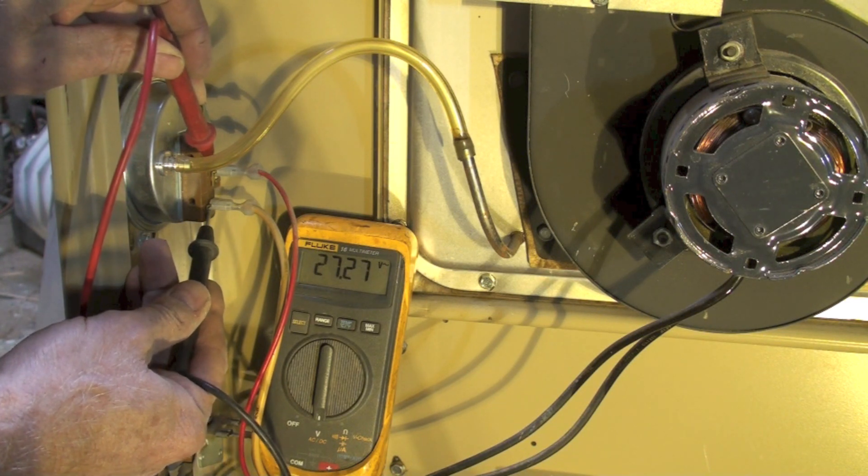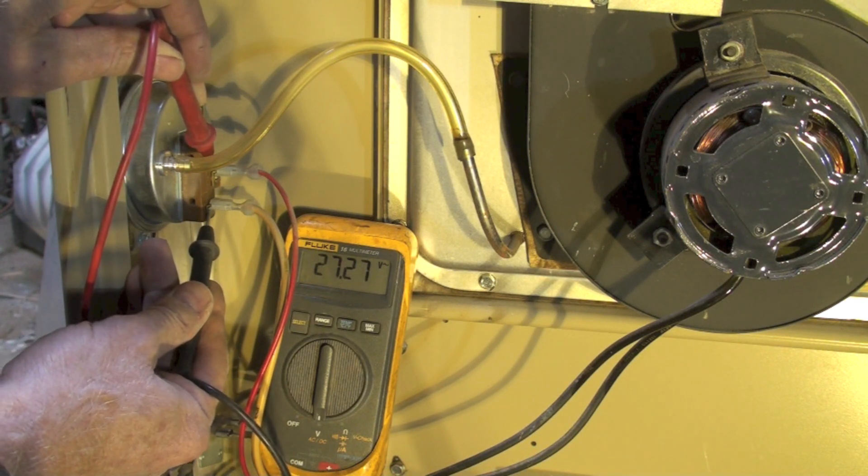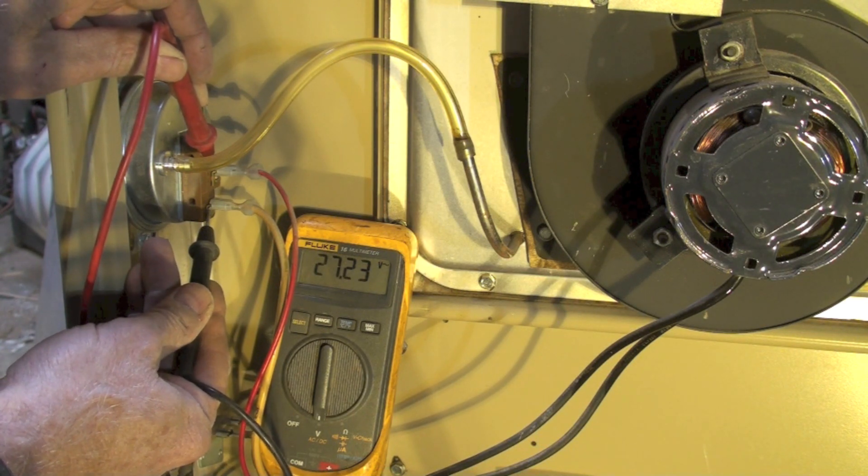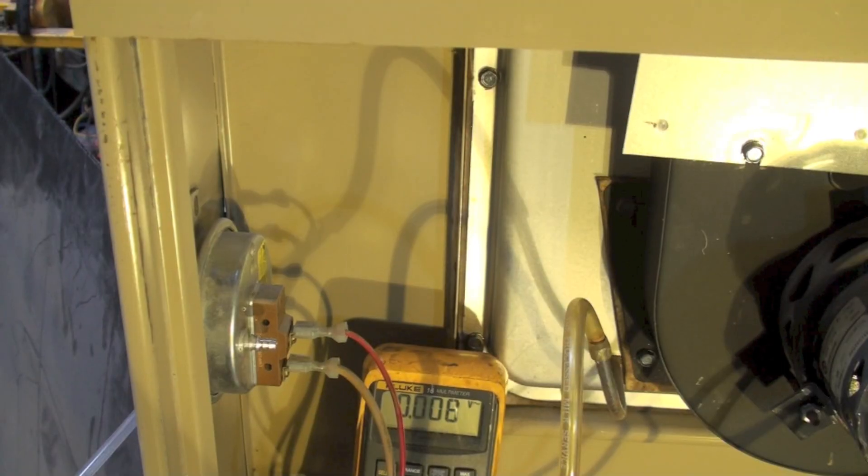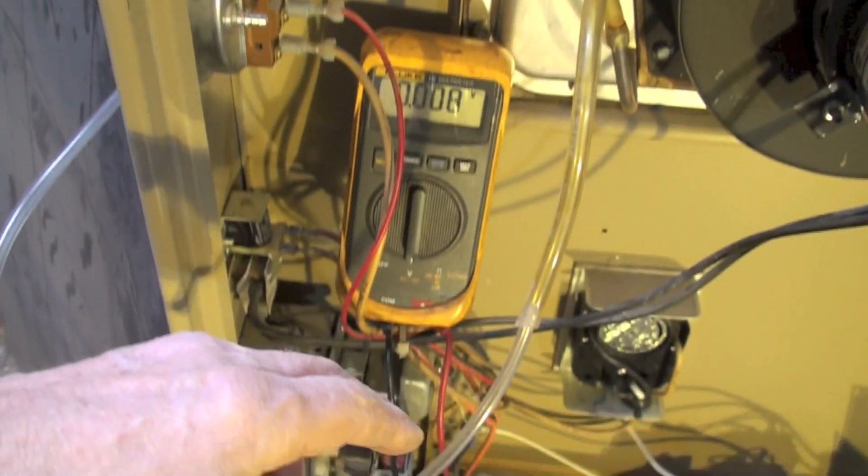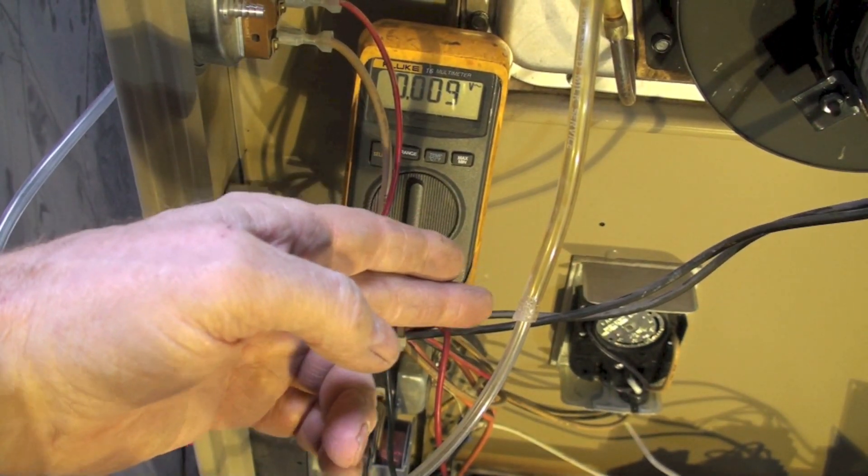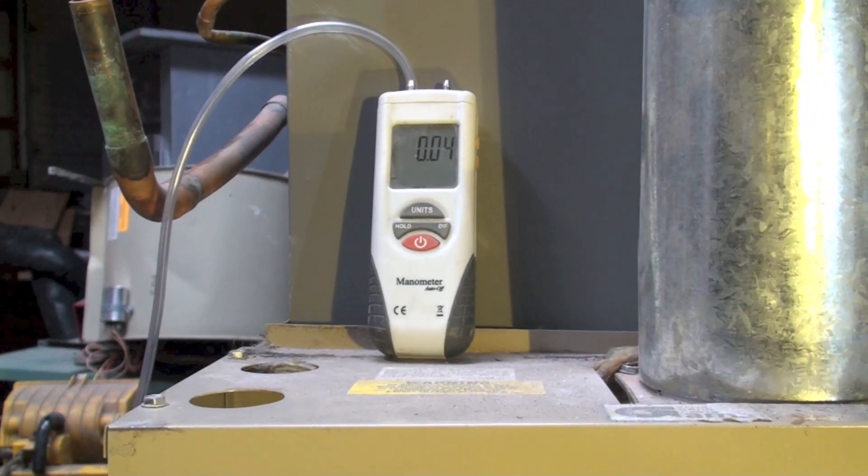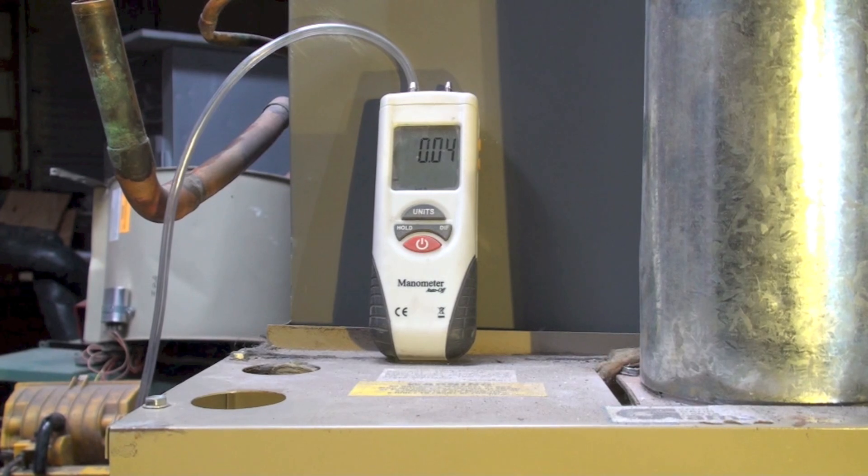Do I replace the pressure switch? Let's find out if we actually have any vacuum. So what I've done is I've taken a manometer, hooked it onto this hose going to the inducer, and I'm showing virtually nothing.